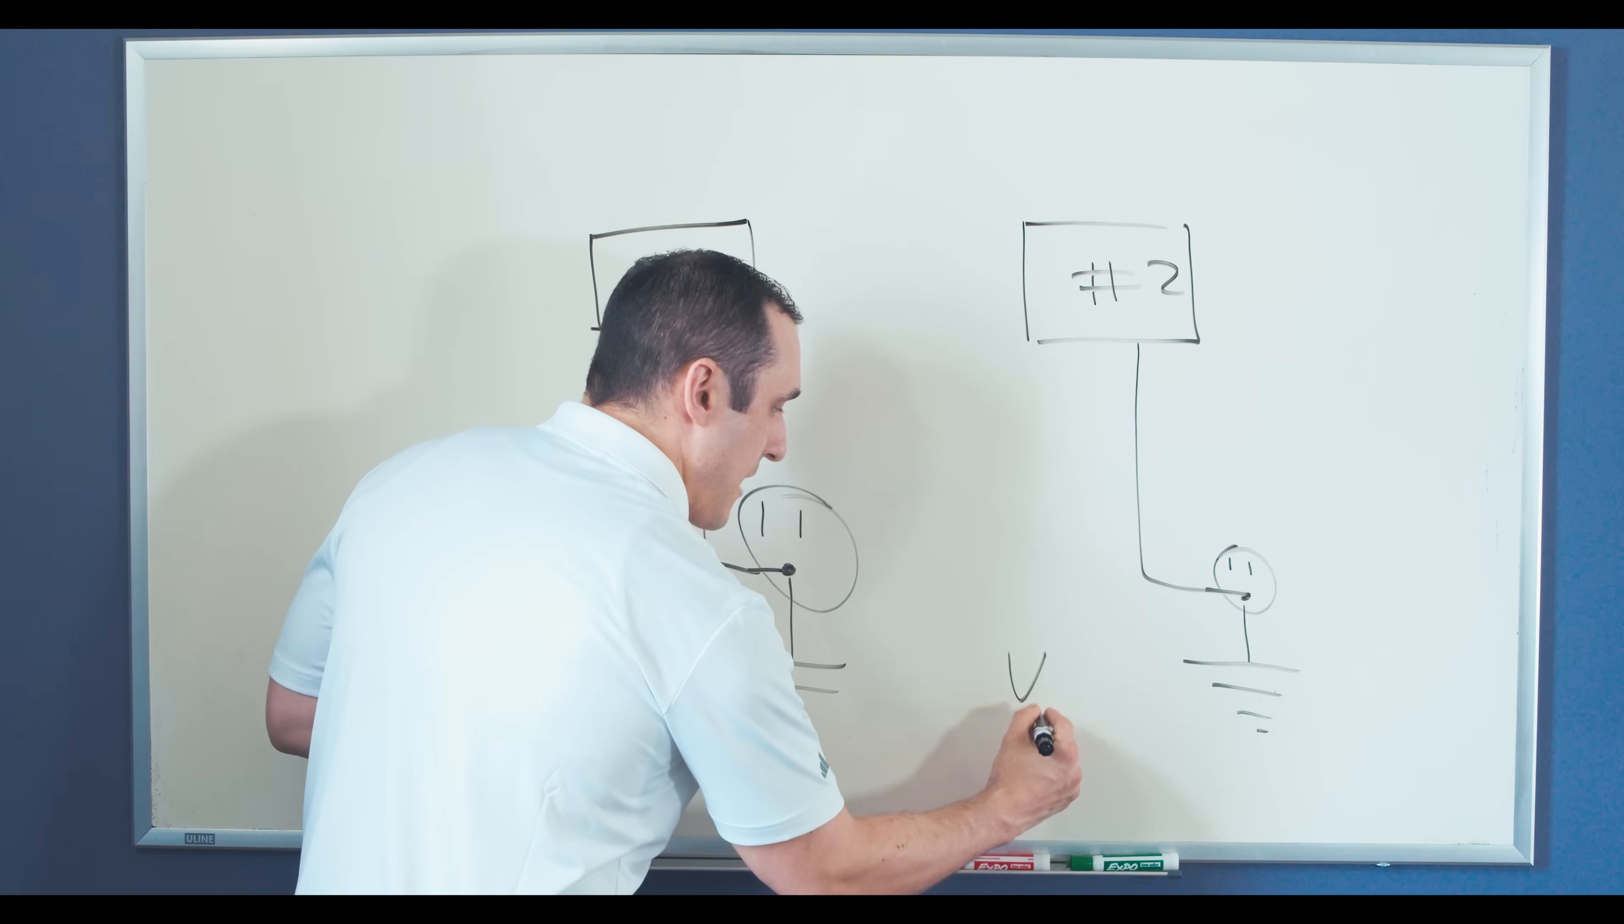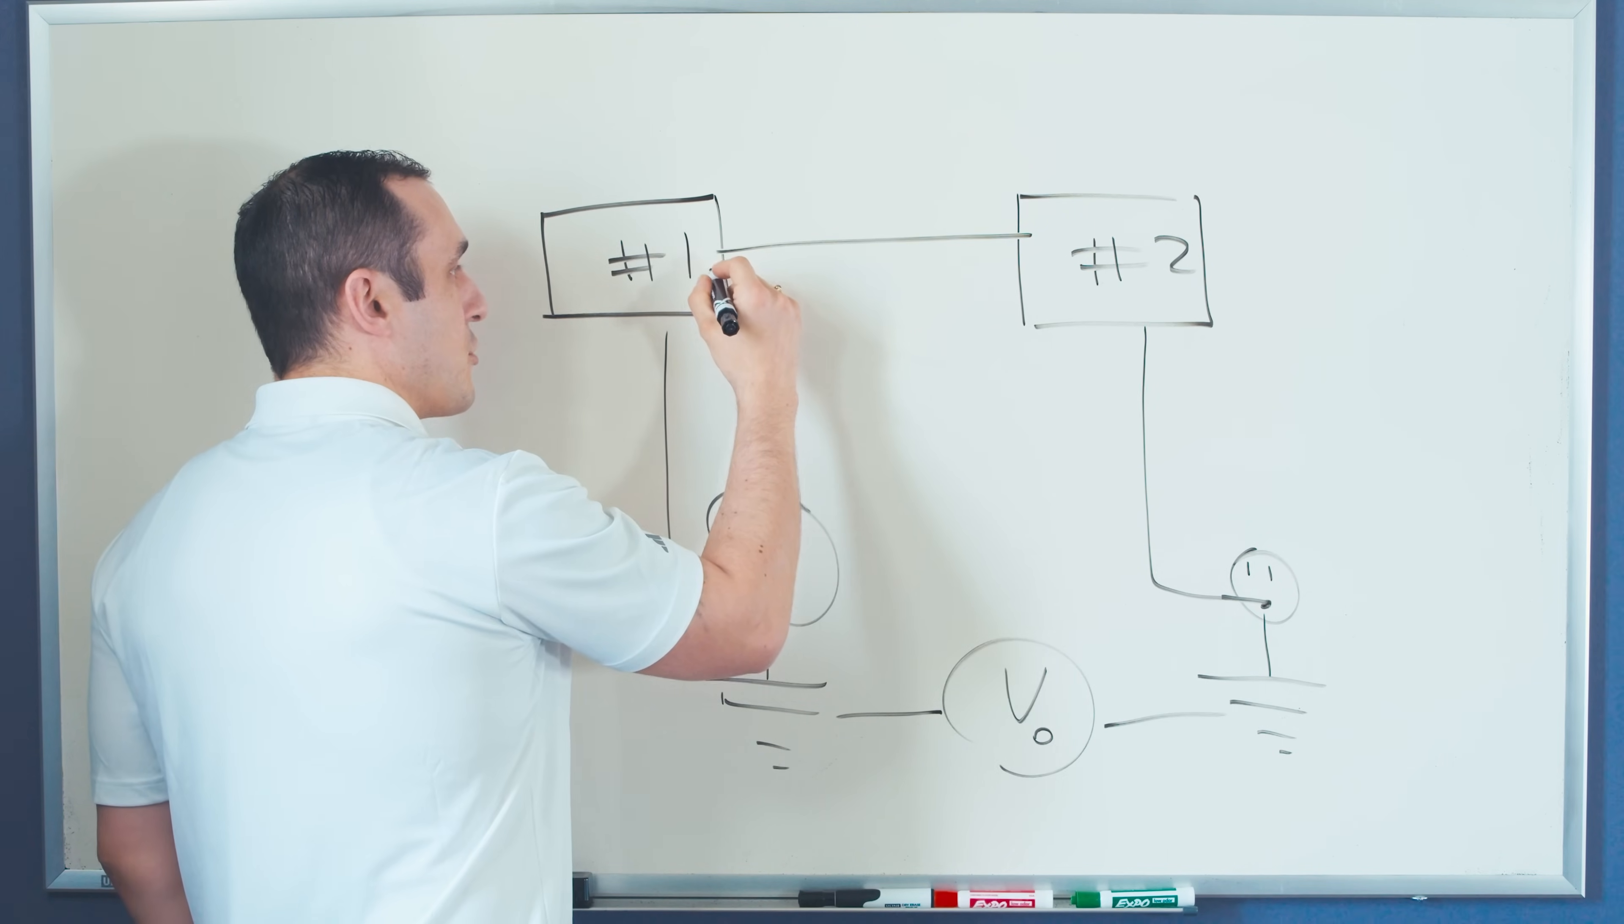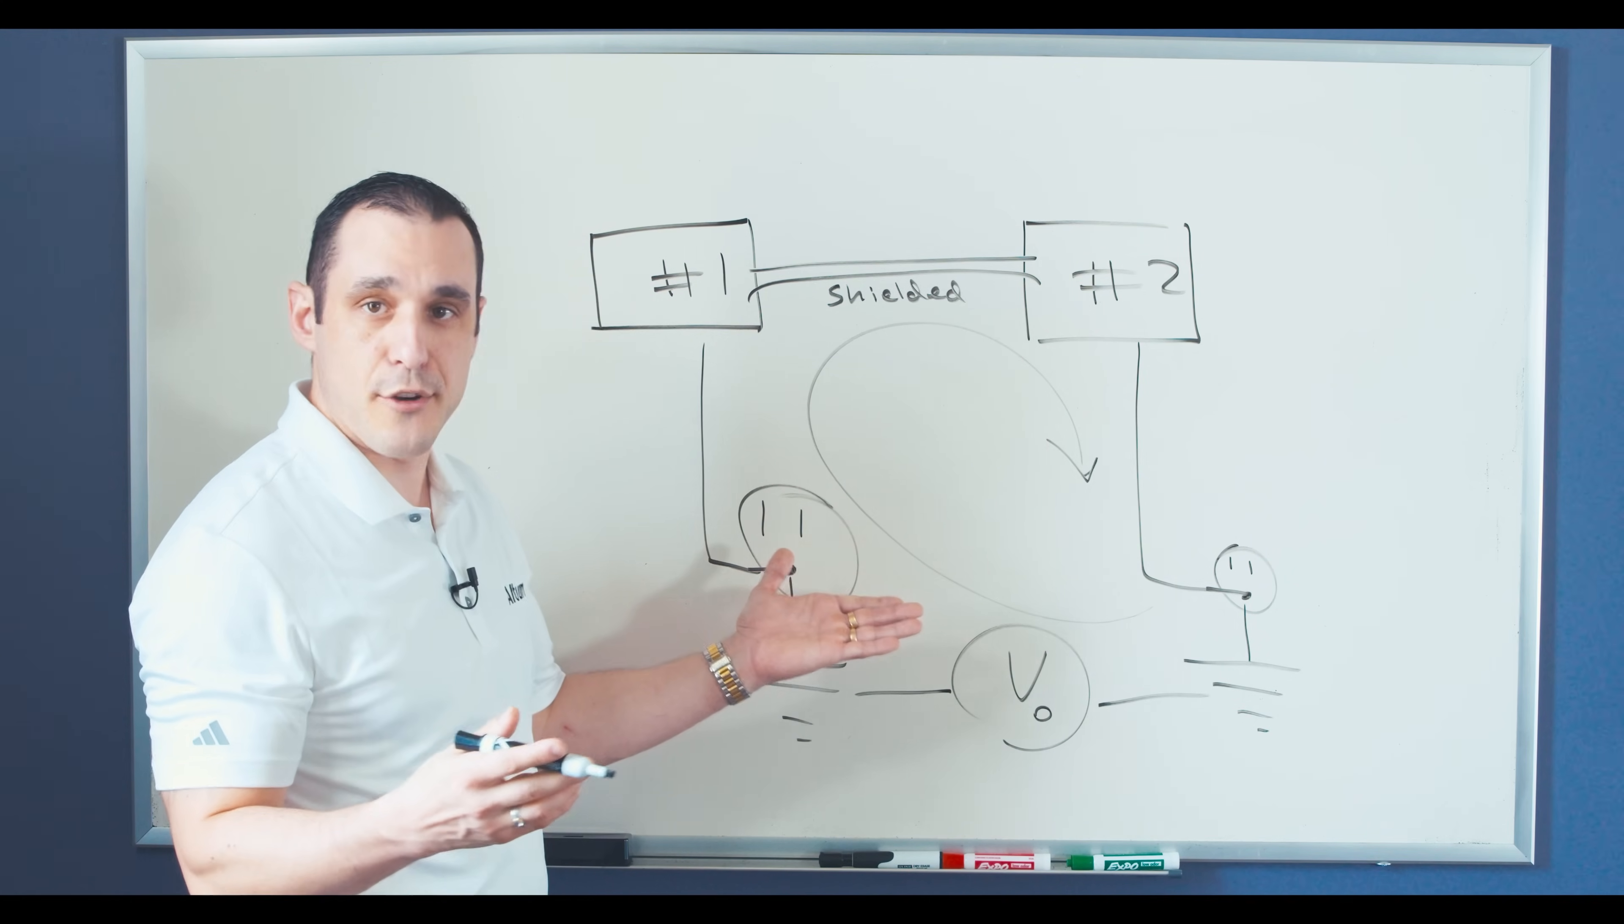And so what you can get is you can get a potential offset that exists between these two earth connections. Just having a potential offset on its own doesn't really matter until you interface these two pieces of equipment with each other. So for example, if we were to run a cable with some signal, and we were then to run a shield alongside that cable, so we have a shielded cable connection between equipment number one and number two, we have now created a big loop here that takes this earth connection on this side, bridges it to this side, and now this voltage offset between these two grounds can then cause some current to flow along this loop. This is essentially a ground loop.